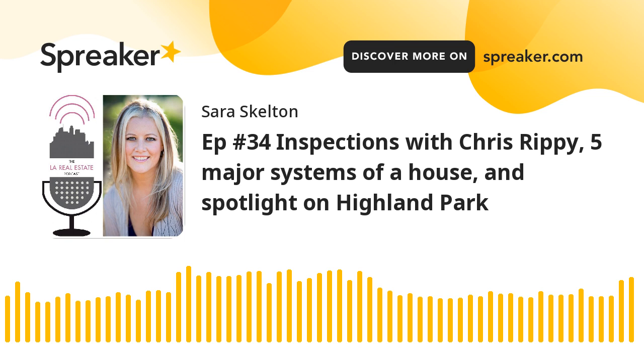Beyond that, it's pretty basic stuff. We're looking for, for instance, you mentioned the double tapping. There are some electricians out there that feel like this is an acceptable practice, but keep in mind, as inspectors, we follow the National Electrical Code, and there is information in there that is clear about not double tapping. Essentially, that is having more than one conductor or wire to a breaker. Obviously, that would be potentially stressing or overloading that one breaker.